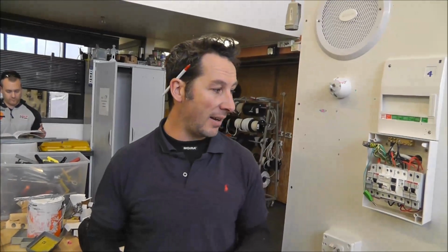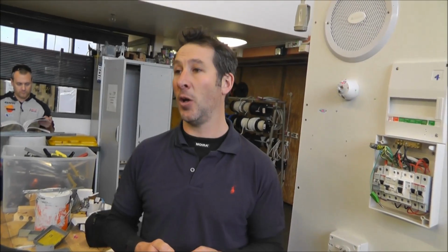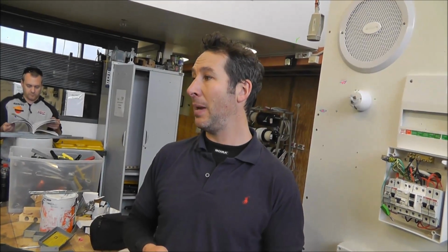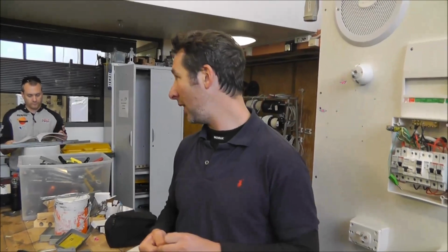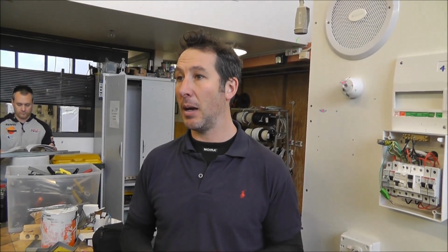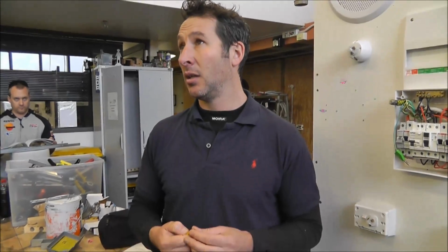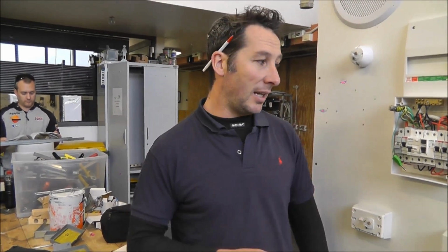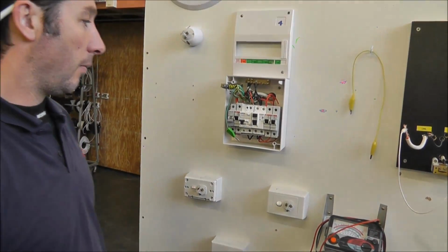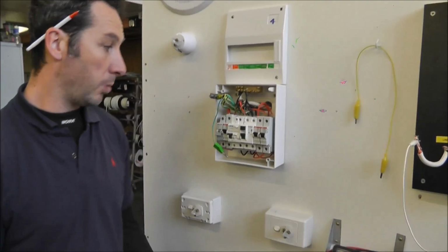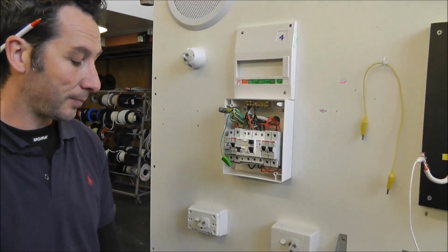Elliot said that the resistance is low enough on the phase and on the earth that would permit the protective device to operate in the event of a fault. Is that what you said? And when do you have to test for fault loop impedance? On circuits that are not protected by an RCD. That's why Matt's got like 89% in theory. So, circuits that are not protected by an RCD.